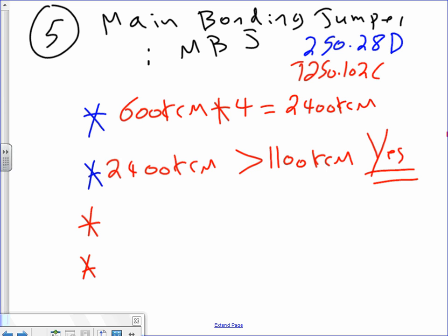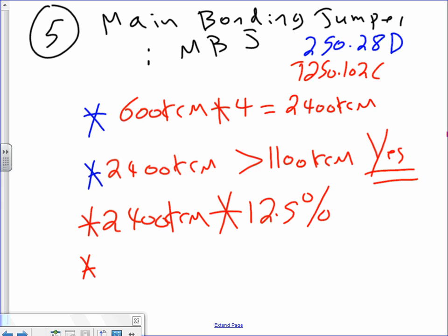So what do you do? You take that number, gentlemen. So you take the 2400 KCM and multiply it by 12.5%. Now where did that come from? Note number 1 under the table. Highlight that one. Note number 1 under the table, guys, will tell you if your math applies.